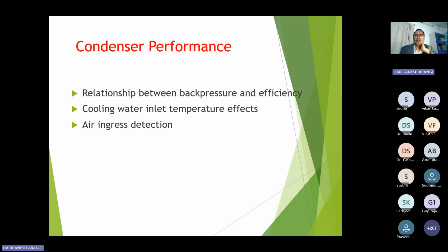Next, coming to the condenser, the cooling water inlet temperature also affects it. As per the design, it should be maintained. If the design inlet temperature is 32 degrees and we are supplying 34 or 36, again the performance comes down. Air ingress detection: sometimes air ingresses from welding leaks or any welding joint failures, and again the vacuum reduces and the efficiency will come down.